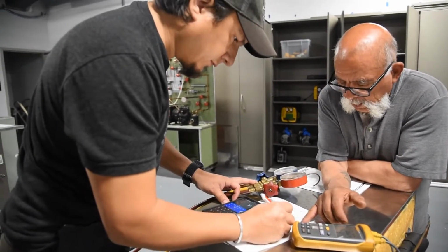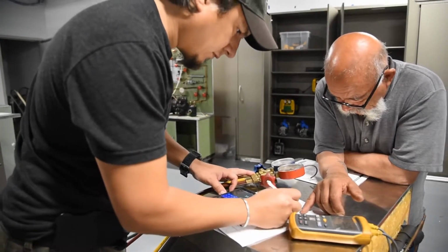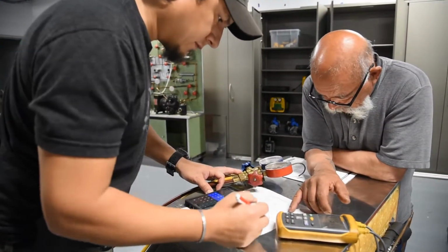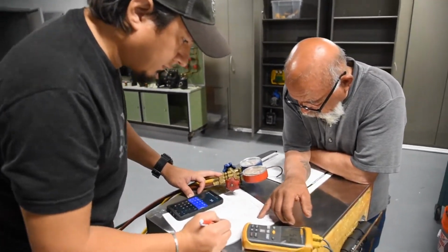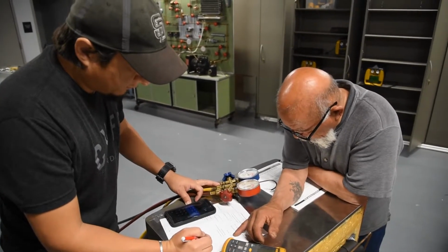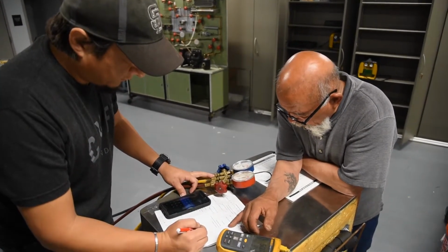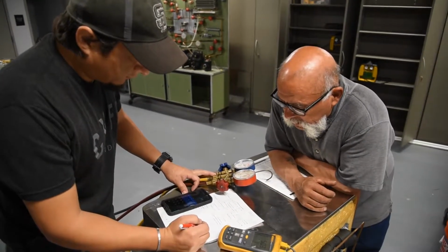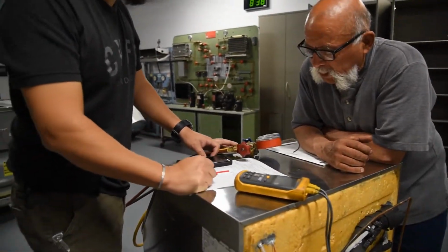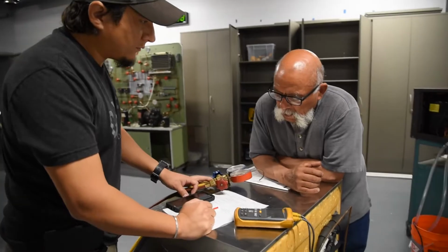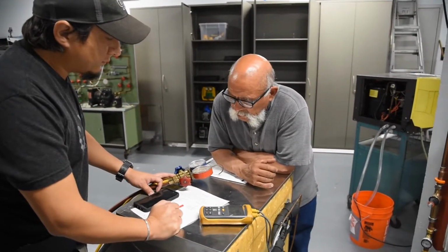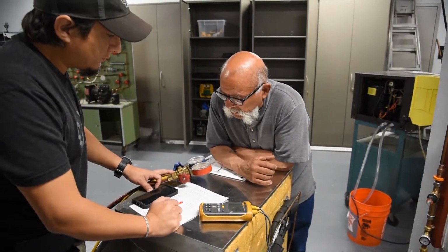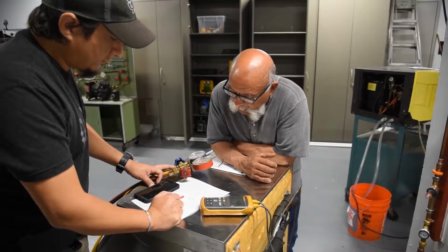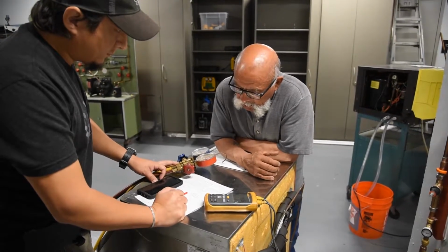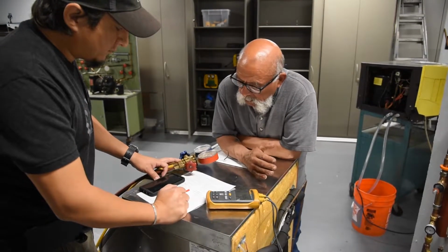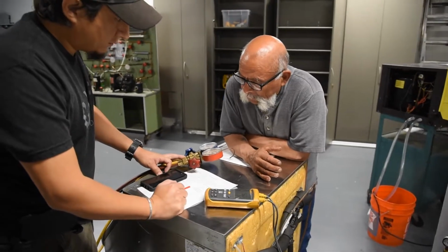Subcooling, superheat. Oh, superheat up here, 46. Now, high superheat means low on refrigerant. High subcooling means there's too much refrigerant. So when you see that situation, there seems to be a blockage in the refrigerant flow. So that's what we would troubleshoot to see what's going on. Okay. But then maybe it's normal for the ice machine to do that. I'm not that familiar with it, so we're going to monitor it for a few more minutes and see what happens.